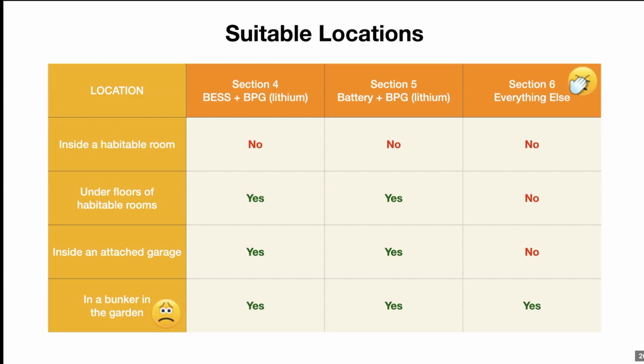When you get to section 6, unfortunately, I call this the trash, even though some of the best products or safest products on the market might fall into section 6. It's because they aren't lithium. So for a start, anything that's not lithium goes into section 6, and any lithium battery that doesn't comply with the best practice guide or hasn't got a manufacturer's declaration to the best practice guide gets thrown into section 6. And it has the most onerous requirements. So you can see it's got a lot of no's there. There's not many places that you can install. I jokingly say, yes, you can put it in a bunker in the garden, but not within a building that contains habitable rooms.